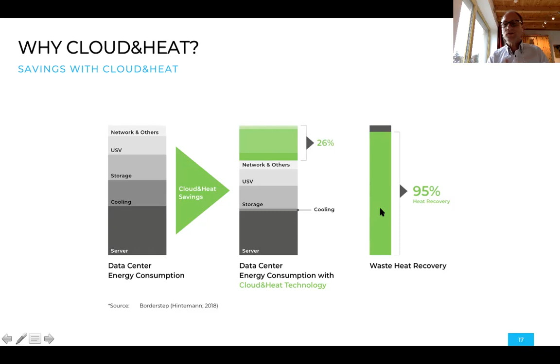In order to do so, you have to certify, of course, the use of this heat. And we managed to get a certificate that this heat that comes from a data center can be regarded as avoided emissions on other heating systems. So the primary energy factor for heat that comes from a data center can be set to 0.0, and this gives the planner of buildings more room to build an efficient building, taking into account that servers are in that building, and he can reuse the energy of those servers.